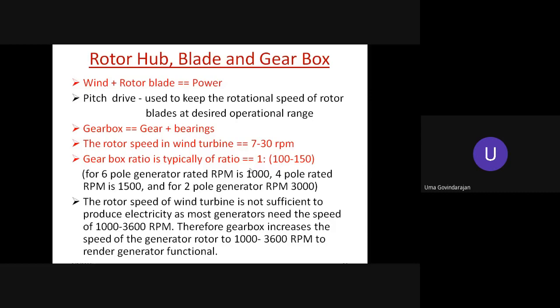So for a 6-pole generator, rated RPM may be 1000. For a 4-pole it is 1500, you all know that. And for a 2-pole it is around 3000 RPM. So for comparison, depending upon the type of generator employed on the other side, you can select the gearbox ratio. The rotor speed of the wind turbine is not sufficient to produce electricity, as most generators need speed based on the number of poles in the machine, which may vary from 1000 to 3000 RPM on the electrical side. Therefore, the gearbox increases the speed of the generator rotor to 1000 to 3600 RPM to render the generator functional.